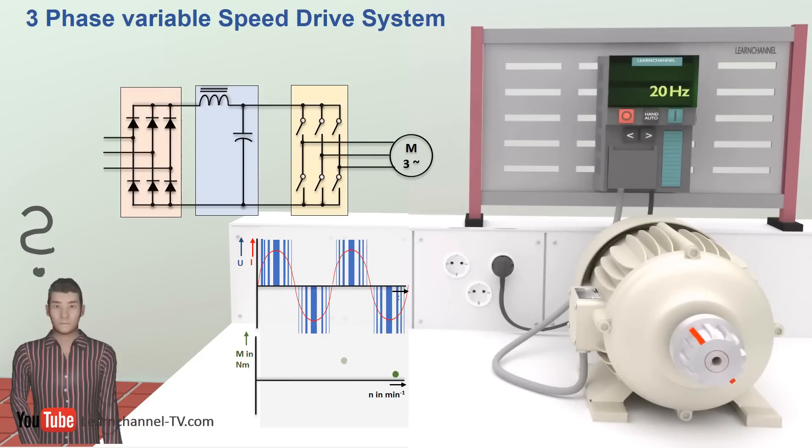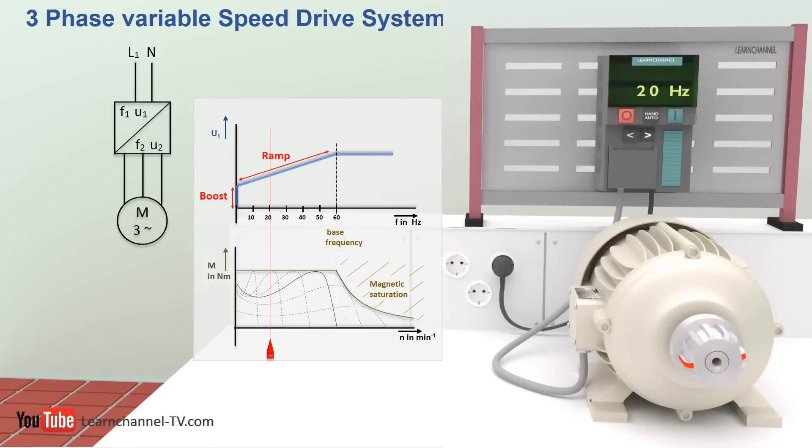But now you have a problem. The inductive reactance of the motor coils rises with the signal frequency. That means you would get less torque. So what is the solution? To overcome this obstacle, you would adapt the voltage to the frequency during acceleration and deceleration.